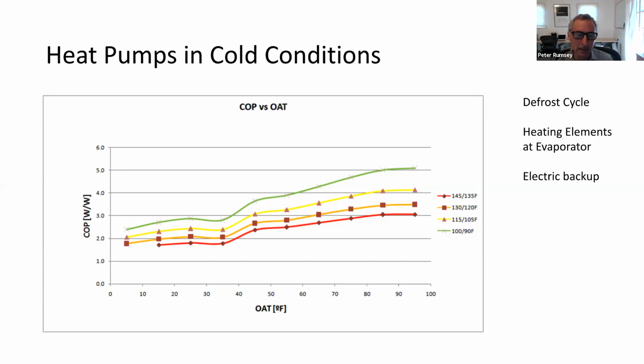Most of the companies that have air source heat pumps will have a defrost cycle where, for a few minutes per hour, they'll run the cycle in reverse and then melt the ice off the coil so it doesn't build up, which would block the airflow over the coils and our ability to pull heat out of the air. When they get down to the colder temperatures around 0 degrees Fahrenheit, most of them stop being able to produce heat because it's just too cold. And a lot of buildings, I work mostly in California, and that's not a problem because we don't get down below 0 very often, if at all, only in the mountains.